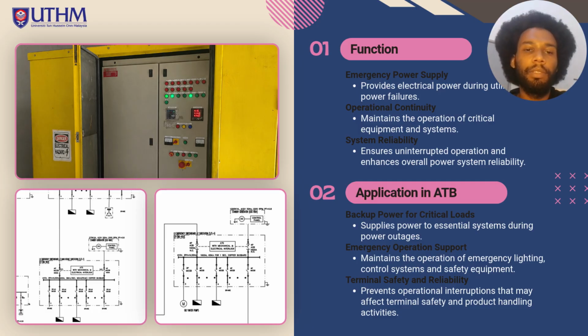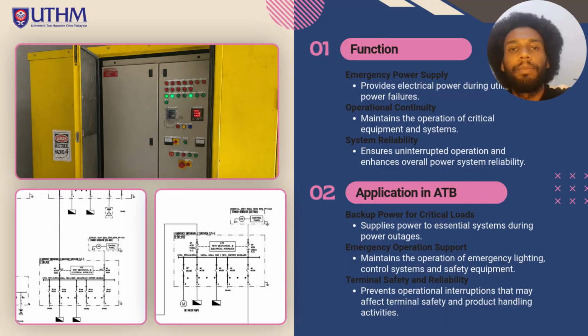So here is the generator function and application. The first part is the function. The emergency diesel generator converts chemical energy stored in diesel fuel into electrical energy. It provides an independent backup power source during mains supply interruptions. So the application in ATB: at ATB, the generator supports critical systems such as emergency lighting, fire protection system, communication equipment, and essential operation loads. The generator works together with the automatic transfer switch to ensure uninterrupted operation of critical equipment.